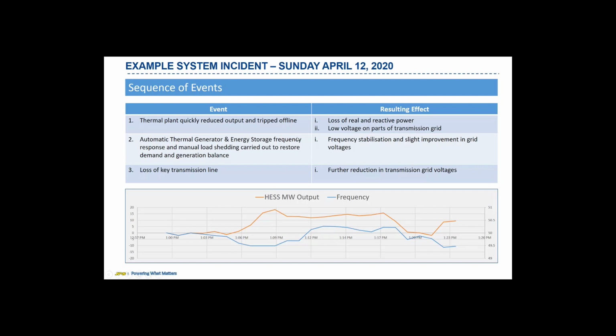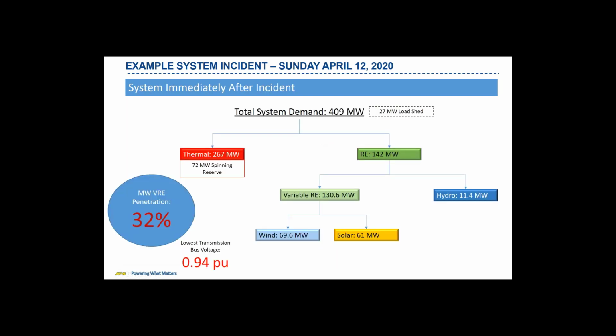All right, so we were not too bad at that point, but then to make the problem even worse, we lost a key transmission line. So this resulted in a further reduction of our grid voltages. So this is an overview of what the system looked like immediately after the incident. Remember that we lost that thermal plant, and we also carried out some manual load shed. So the total demand is a bit lower than it was before.